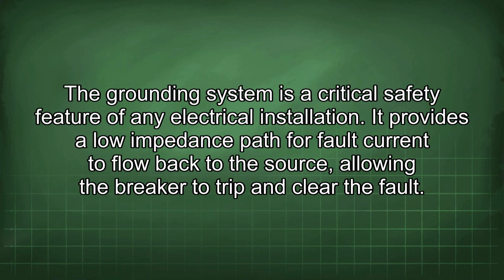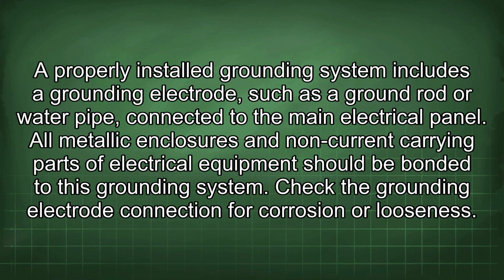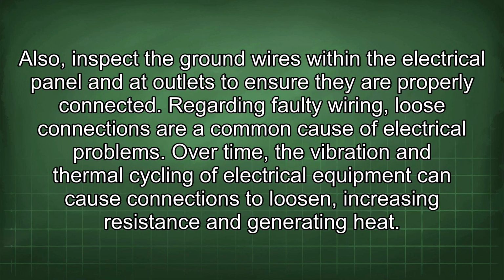The grounding system is a critical safety feature of any electrical installation. It provides a low impedance path for fault current to flow back to the source, allowing the breaker to trip and clear the fault. A properly installed grounding system includes a grounding electrode, such as a ground rod or water pipe, connected to the main electrical panel. All metallic enclosures and non-current carrying parts of electrical equipment should be bonded to this grounding system. Check the grounding electrode connection for corrosion or looseness. Also, inspect the ground wires within the electrical panel and at outlets to ensure they are properly connected.